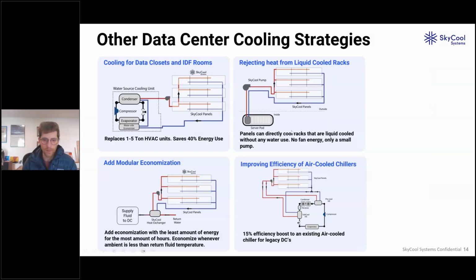But there are immersion data centers, which you're starting to see, where you have direct liquid cooling of computers, and that's maybe what you're seeing in this top right corner. The panels can be used to essentially directly cool the fluids in these pods or immersion tanks. You can combine the system with CRAC units or water source cooling units, essentially using the panels to directly cool a condenser or replace a condenser, and then they can economize by directly cooling the air when it's cooler outside. And then you can use it for the direct cooling, which I just mentioned. We have a chilled water loop, and the panels are just cooling the water circulating through the system.